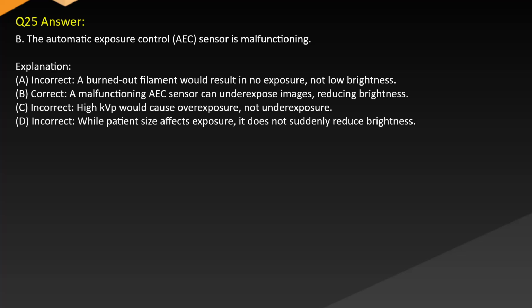Answer B. The automatic exposure control (AEC) sensor is malfunctioning. Explanation. A. Incorrect. A burned out filament would result in no exposure, not low brightness. B. Correct. A malfunctioning AEC sensor can underexpose images, reducing brightness. C. Incorrect. High kVp would cause overexposure, not underexposure. D. Incorrect. While patient size affects exposure, it does not suddenly reduce brightness.